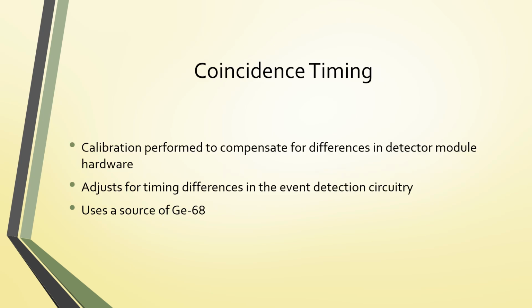Now, coincidence timing. This is a calibration that's performed to compensate for differences in detector module hardware, and this is going to adjust for the timing difference in the event detection circuitry. And you want to make sure that you are able to accept counts within a certain timing window and that those are synced up between the different detector modules. This usually uses germanium-68 as a source as well.